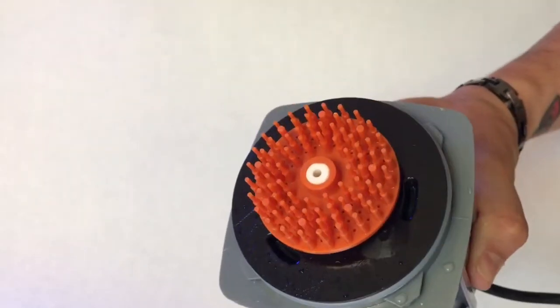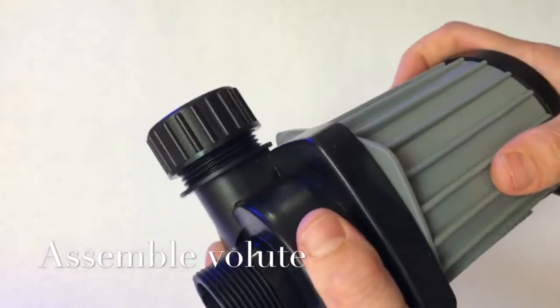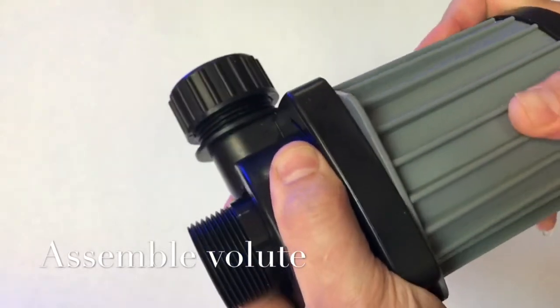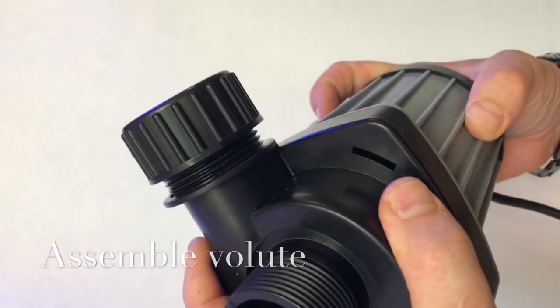Now we're ready to reassemble the volute on the front of the pump. To do so, start at a slight angle and press them firmly together before trying to twist. Once they're tight, give it a good turn.